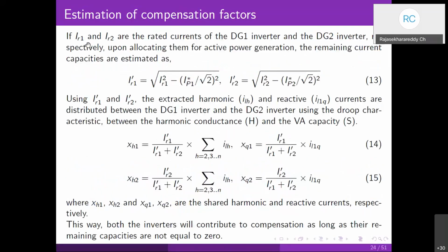Here, IR1 and IR2 are the rated currents of the DG1 inverter and DG2 inverter respectively. Upon allocating part of their capacity for active power generation, the remaining current capacities are estimated like this. Using IR1 prime and IR2 prime, the remaining capacities, and the extracted harmonic and reactive currents, we are going to estimate these compensation factors.